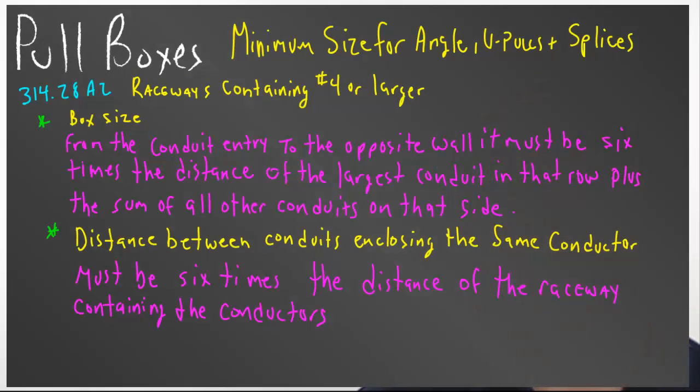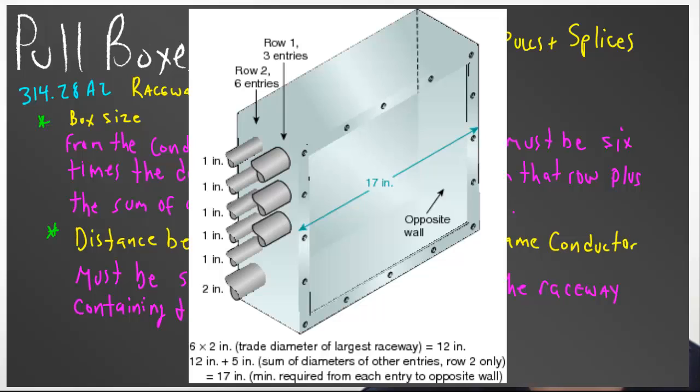When we get into angle, u-pulls, and splices the rules change a little bit. The rules are it's 6 times the largest conduit on a side to the opposite side of the box plus the addition of the conduits that are also on that side in the same row. When you look at this graphic you'll see that we have a 2-inch and 5 1-inch conduits. Well 6 times that 2-inch is 12 inches and then when you add the 5 1-inch conduits which would be 5 inches that box to the opposite side would have to be 17 inches. You don't have to count those other conduits in the second row because the conduit in the last row has more conduits in it and it would require the box to be larger. Keep that in mind.